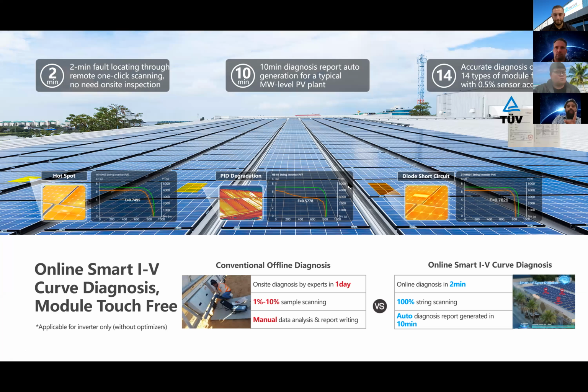So what's happening now at the moment is, for a 20 panel string, for example, if you run an IV curve analysis, this will show you which inverter, which string has what problem. So you can shortlist 20 panels, 100% string scanning, and that report is generated in less than 10 minutes.